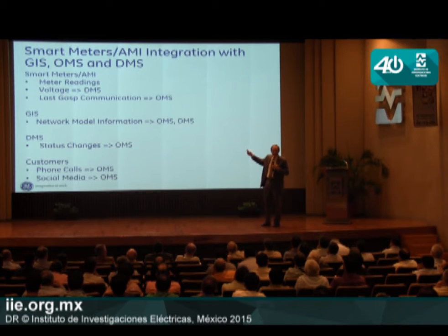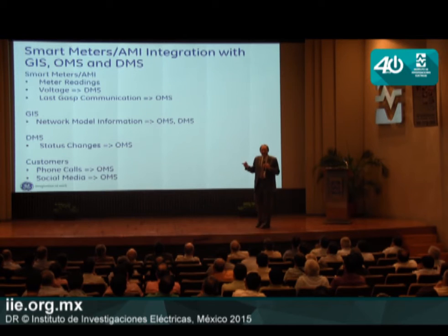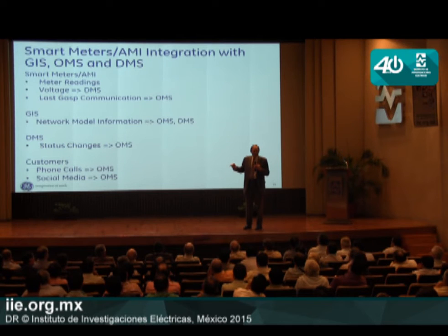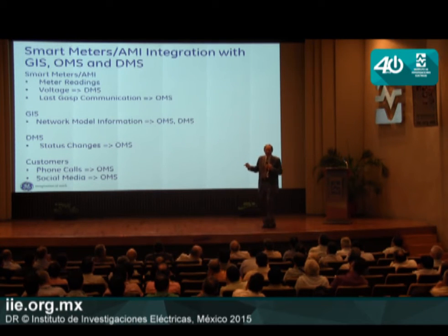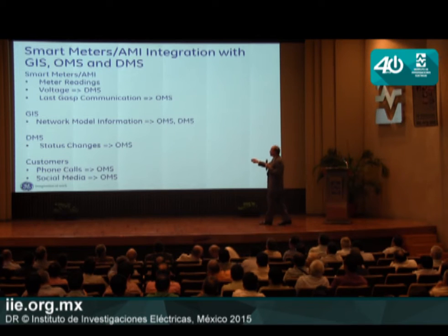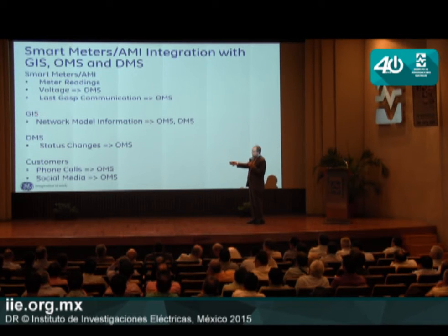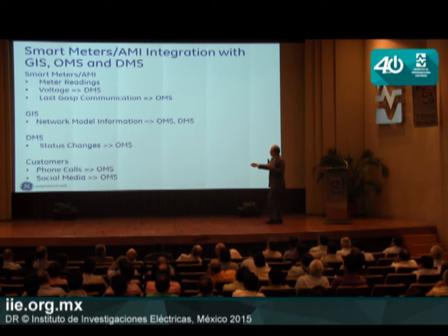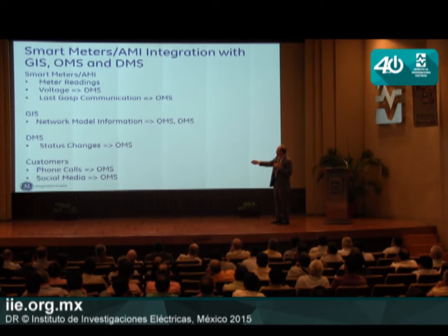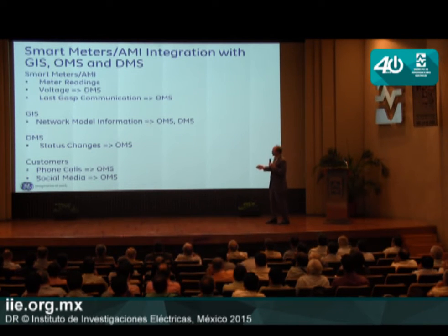Our smart meters will tell us every single customer that's without electricity and the time it occurred, automatically. That's very key, because before a utility can start restoration, what's the first step? Assessing the extent of the damage, right? How many customers are without electricity, and where are they located? This helps tremendously. The geographic information system is your reference system for the network model, for outage management and distribution management. That's your reference system, and it must be kept up to date as construction changes are made in the field.